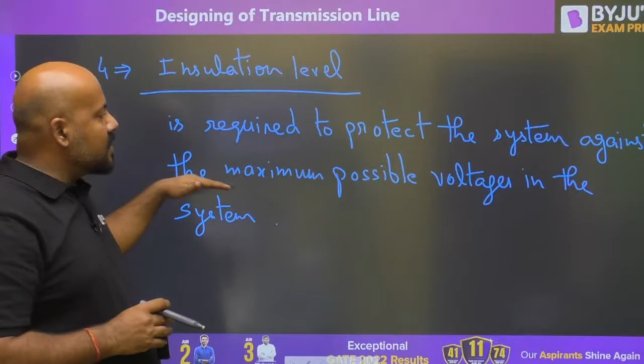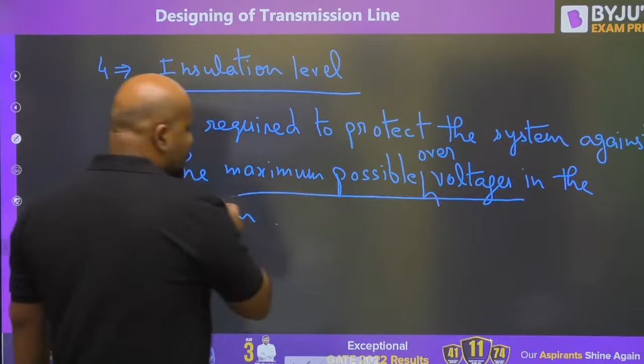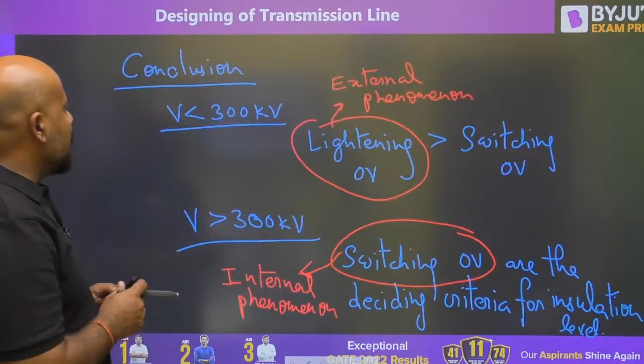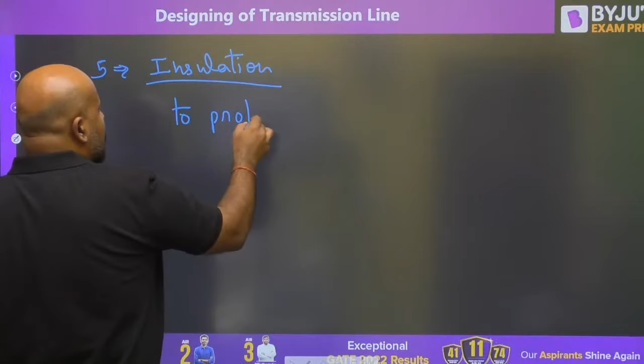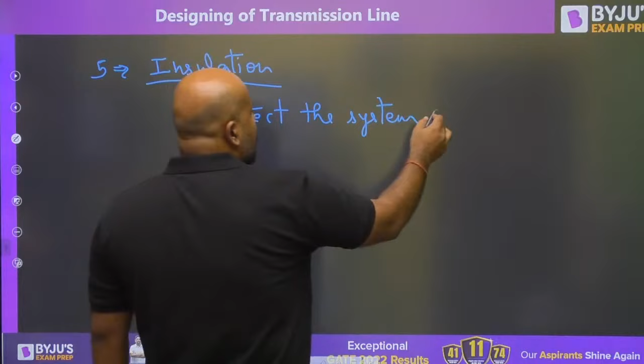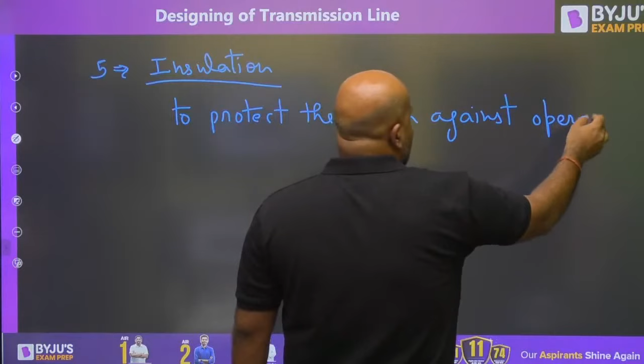When we have defined insulation level, we are saying it is required to protect the system against the maximum possible voltages, or maximum possible over voltages in the system. But when we talk about insulation, we are trying to protect the system against operating voltage.